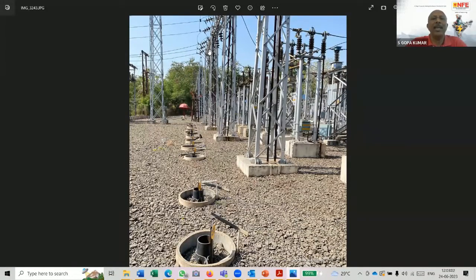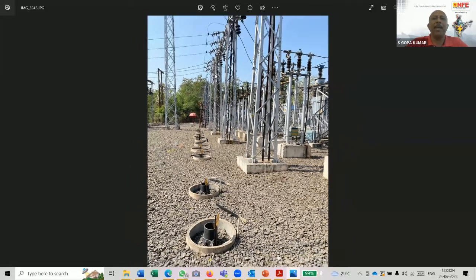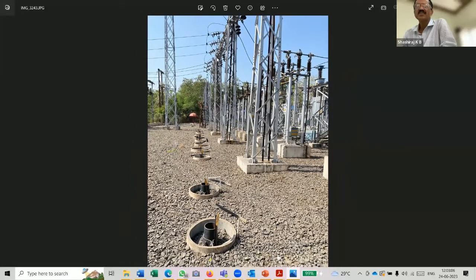The surge arrestor is at the top of this particular line, and a separate conductor, insulated, is not touching anywhere. Separately, it is running and connecting to this particular earth electrode. The length of the earth lead in this case is approximately 5 to 6 meters, and this is the practice followed almost all over India. James Kutty, sir, what is your say on this? Will it work?